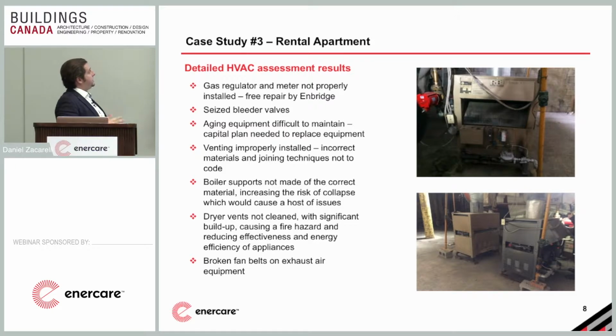The seized bleeder valves on these boilers, we noticed, because these boilers had not been maintained, the bleeder valves had corroded and seized. Simple maintenance, simple quick things that a technician comes out and does, helps prevent these issues from happening. And because these bleeder valves seized, you're not able to continue to maintain this equipment anymore. So it almost ends up being, if I touch it, it falls apart. So you leave it in there until it dies, but then it dies and my tenants don't have hot water. What do I do?